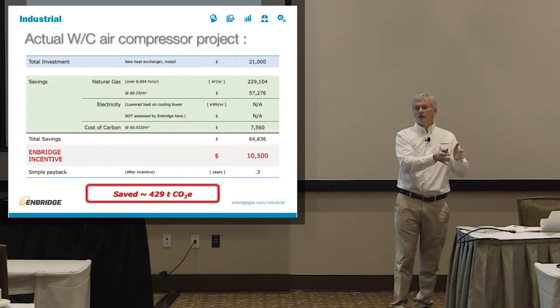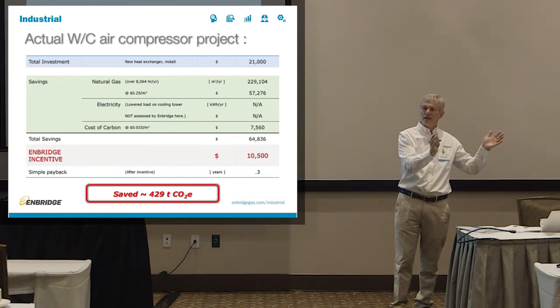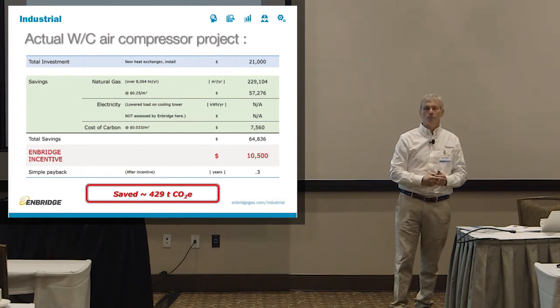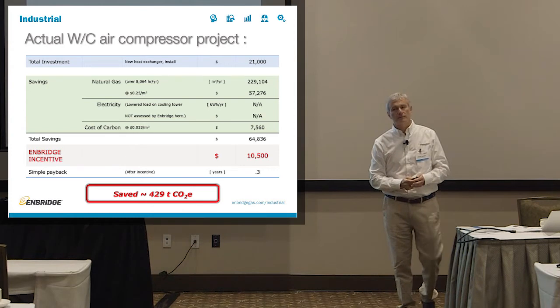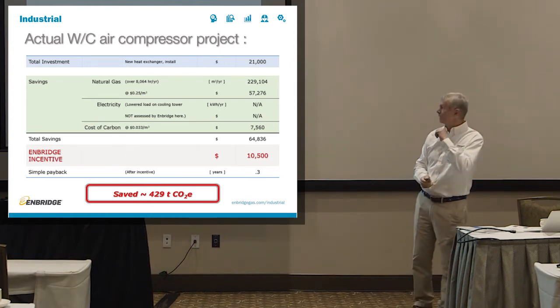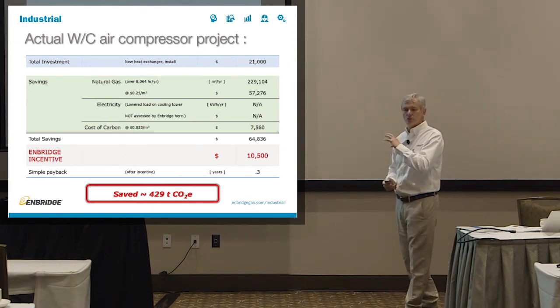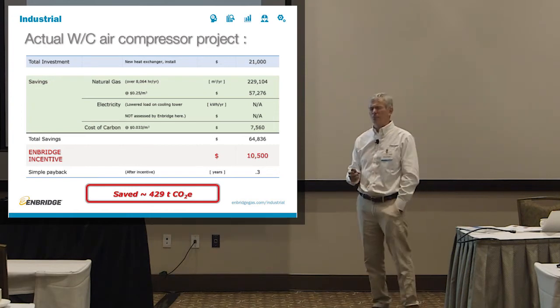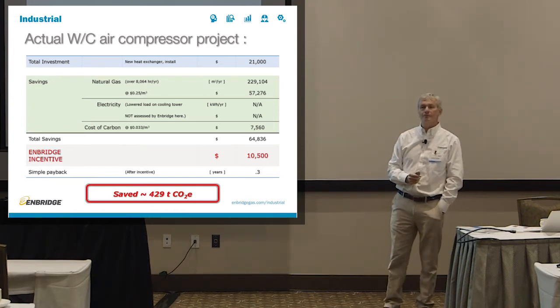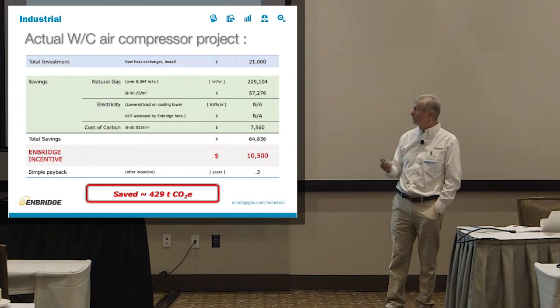All we did is put a heat exchanger in between, so the water that has gone through the compressor, before it goes back into the cooling tower, goes into the heat exchanger and preheats the makeup water for their boiler that runs 8,000 hours all the time. Everybody's happy. 230,000 cubic meter savings. And this was, I believe, a 300 horsepower compressor. So, simple as that.